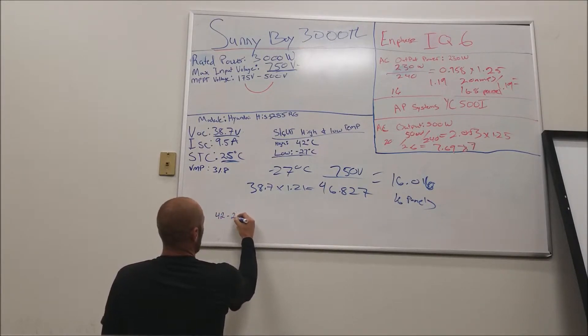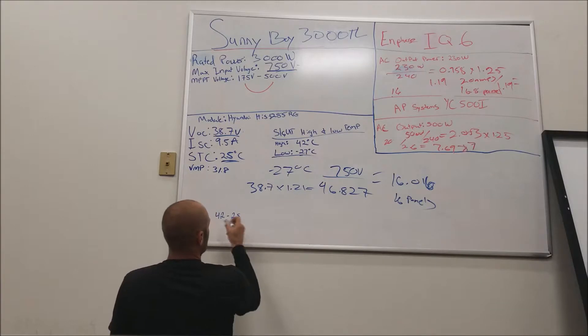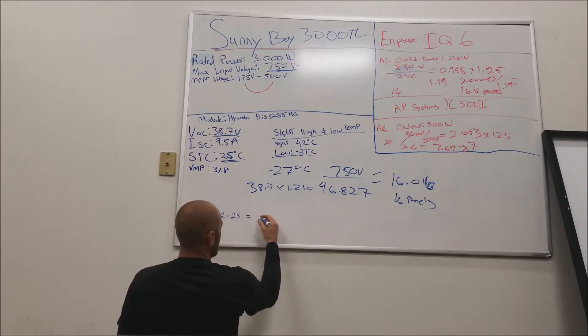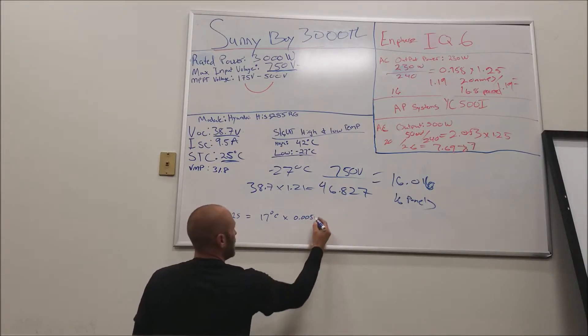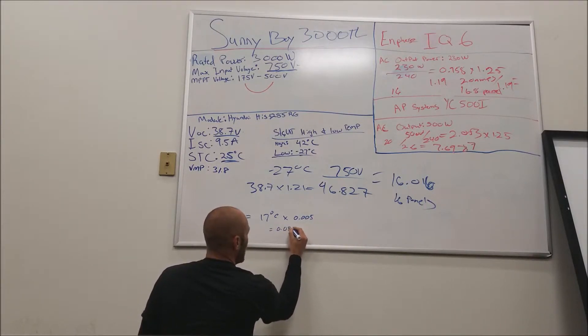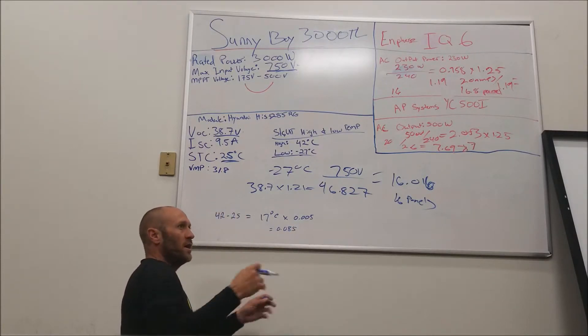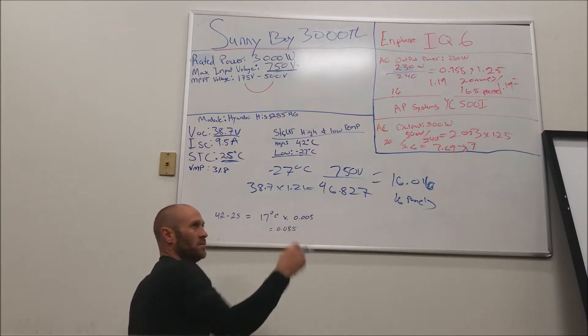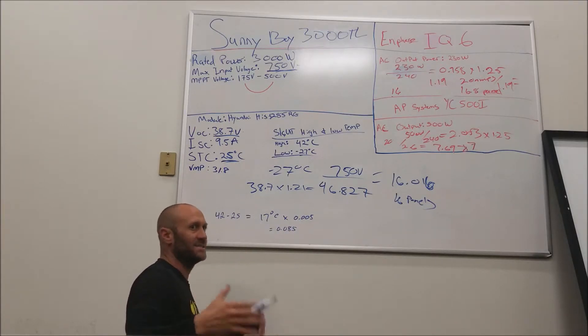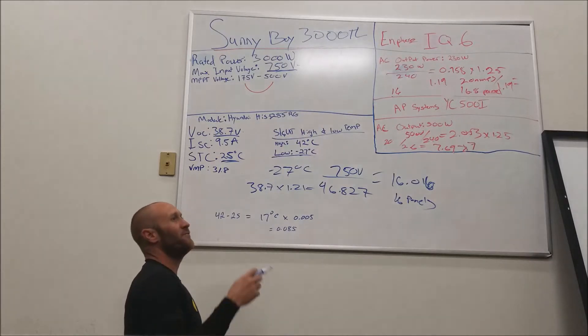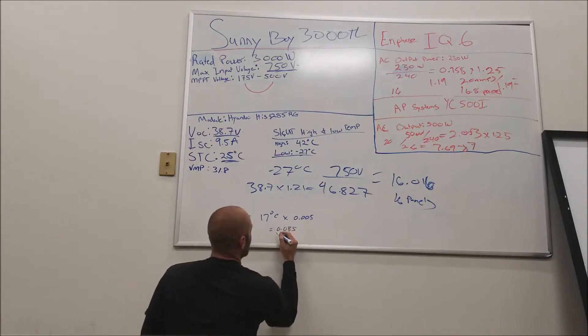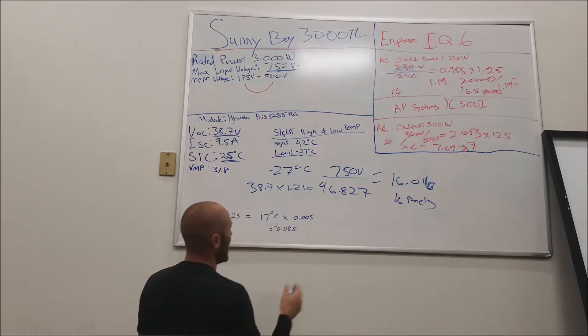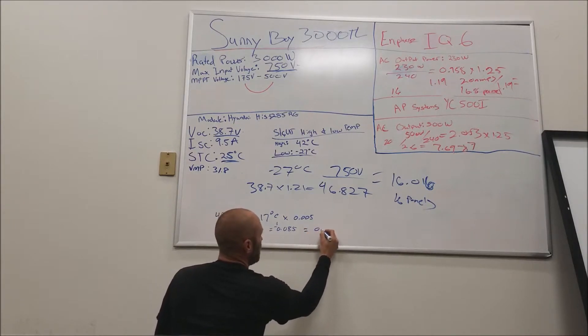42 minus 25 — your high temperature minus your standard testing conditions — equals 17 degrees C. Hit that with your 0.005 factor: 17 times 0.005 equals 0.085. Now, if it's getting colder the voltage goes up, so you add one. But it's hotter, so you don't add — you subtract. One minus 0.085 equals 0.915.